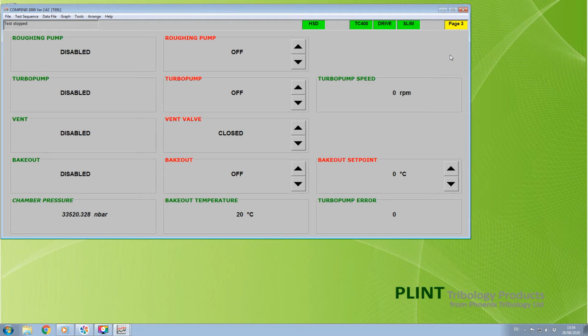If an error condition is triggered, the response on the screen will appear as disabled. An error code will be displayed in the turbo pump error box. Refer to the Pfeiffer vacuum documentation for a description of possible error codes. Vent admits air into the chamber via the intermediate stage of the turbomolecular pump. The solenoid valve will not open until the pump has slowed to below 30,000 RPM. Hence, there may be a delay between switching the valve to open and the response indicating that venting is enabled.